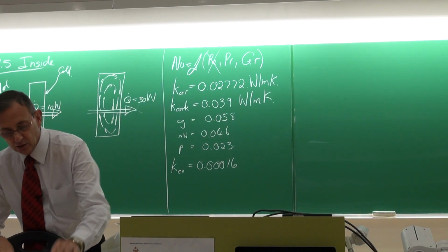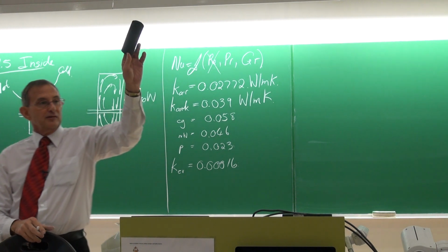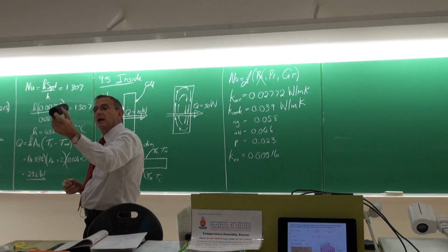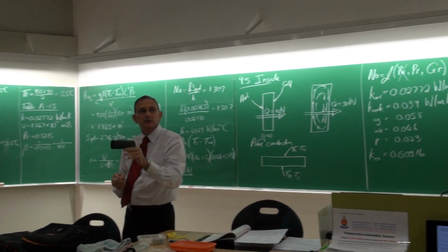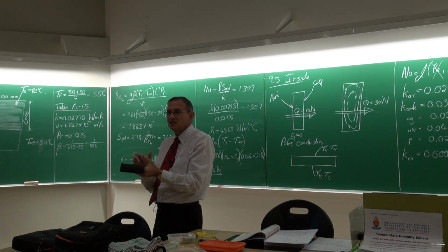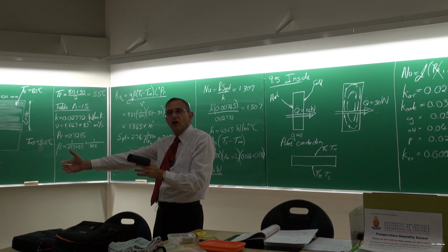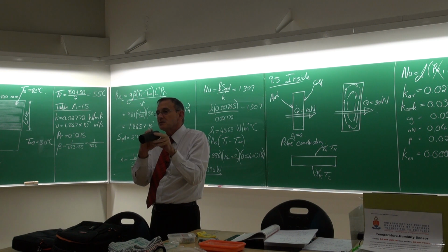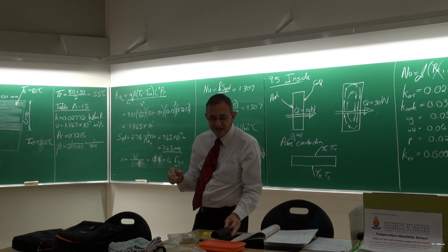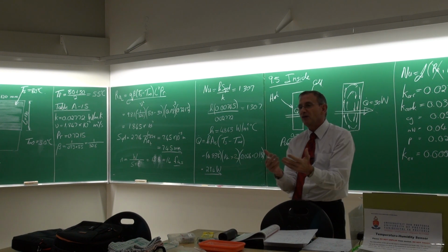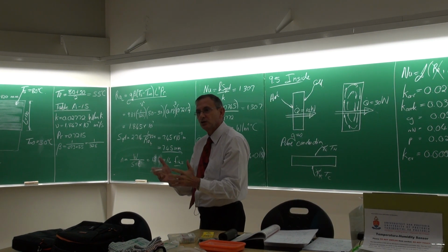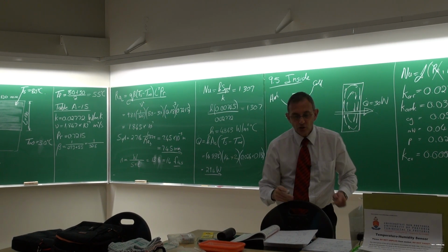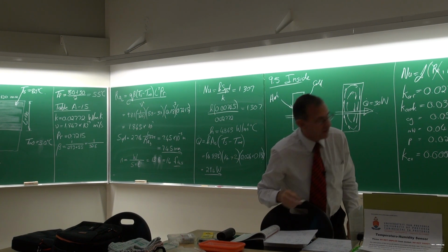In our laboratory, we do lots of heat transfer experiments. I don't know if you've seen this type of material. We call it Armaflex. Okay. And we typically use this as a material on surfaces which are being heated to about 60, 70 degrees Celsius in an environment of 20. Now we need to put on about 300 millimeters thick of this on the tube so that we can decrease the losses to the environment to about less than 1%, just to give you an idea. So Armaflex has a K value of 0.036.